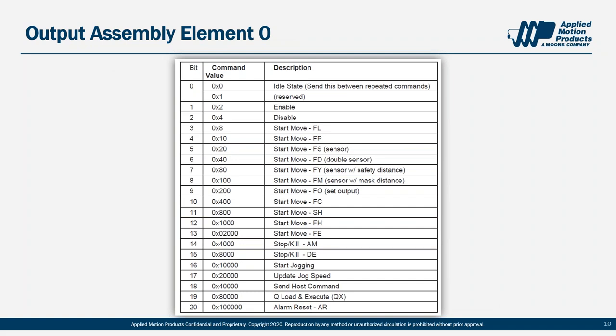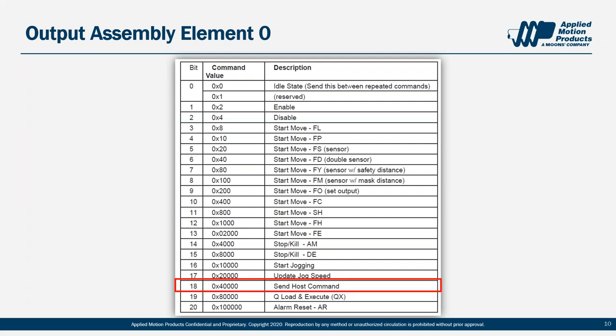Zooming in on element 0 — the command word — this is how we actually kick off the move. The move can be started by a rising edge on the FL bit, which is bit number 3. The sequence of events: make sure element 0 has been cleared for at least one RPI interval, then pull bit 3 high to create that rising edge, hold it high for at least one RPI interval, and then drop it back down. Bit 18 allows access to a whole array of SCL commands while still maintaining the ease of use of implicit messaging.